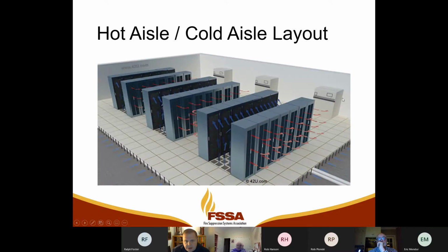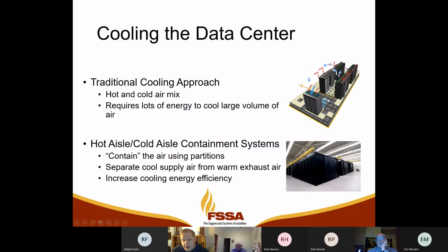And frankly, the other picture was too, having CRAC units, computer room air conditioning units. Sometimes you'll say Liebert units. Probably some of you have heard that term. Liebert's a brand name. This has got a cooling coil in it and a fan, and it blows air down into this raised floor system, just like what's happening here. And then we use the raised floor system as a plenum to distribute air up through perforated tiles. So we blow the cold air right into the cold face of the servers. It goes through, and we have warm air that eventually makes its way back to the return air inlet of the CRAC unit, and it gets cooled back down again and blows in.